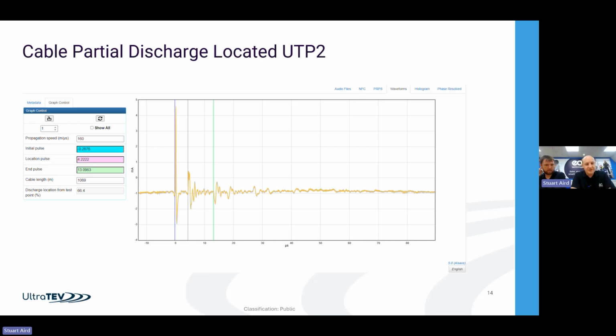So the recommendation is to retest in maybe 3 or 6 months time and see if it's increasing. They can prepare for an outage and get a jointing kit ready just in case it does fail between that time. But we have historically monitored cables with these kinds of levels for a longer period of time. In that case, they can easily go back with their UltraTEV Plus2 and take these measurements, send them to us across the managed survey platform, and we can analyze it and start to trend this level over the coming months.